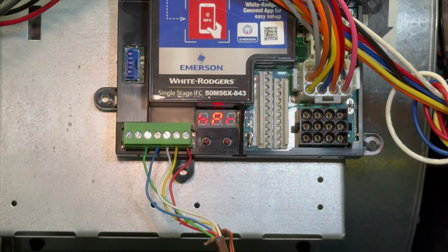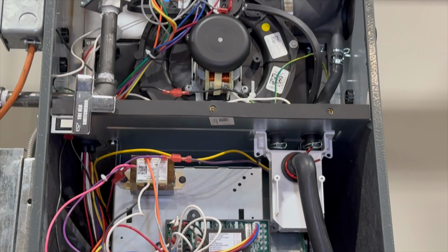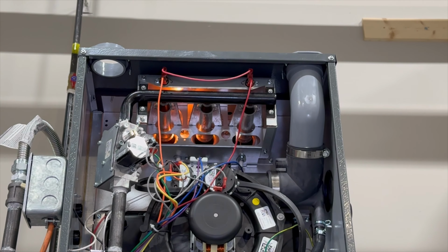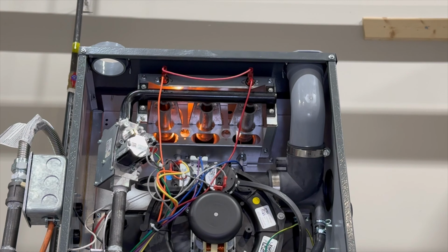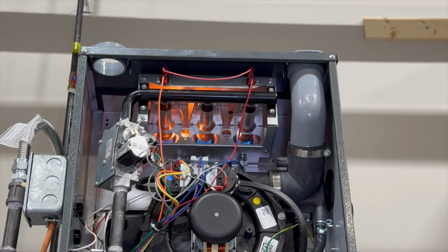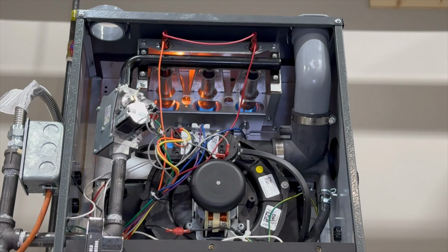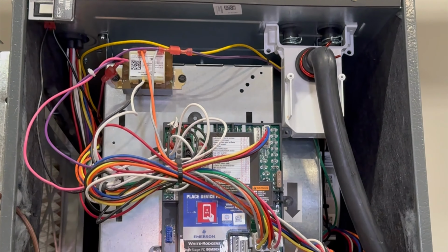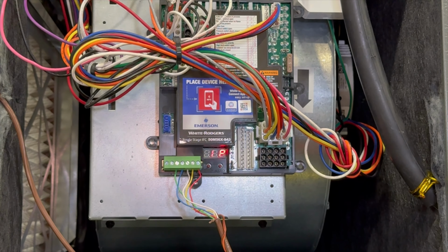During the firing of the heat, the readout will say HPR, standing for heat pre-purge, and the 20-second pre-purge will occur. After the pre-purge, the control will read IGN, indicating that the igniter is turned on, and you will physically see the igniter glow during this process. Once the igniter glows and the gas comes on, it will verify that there was flame present.